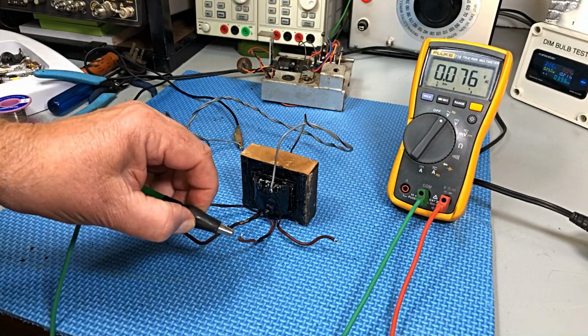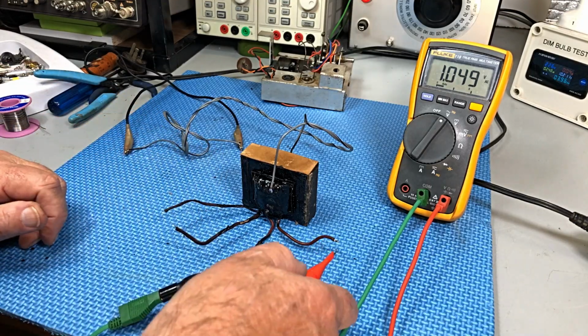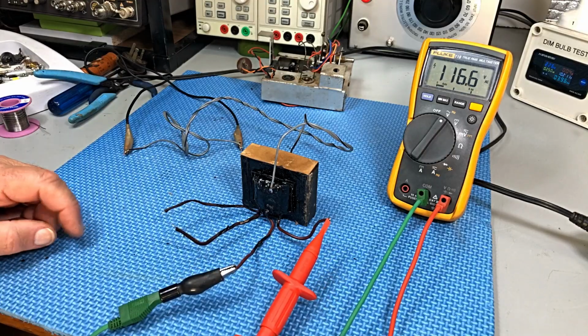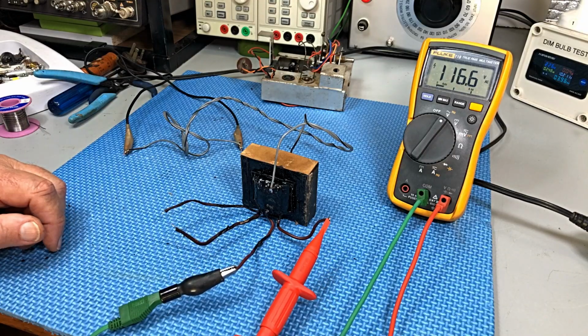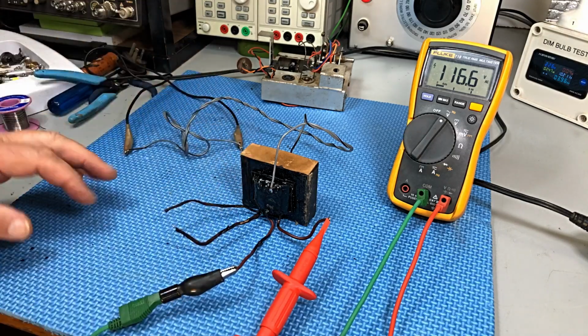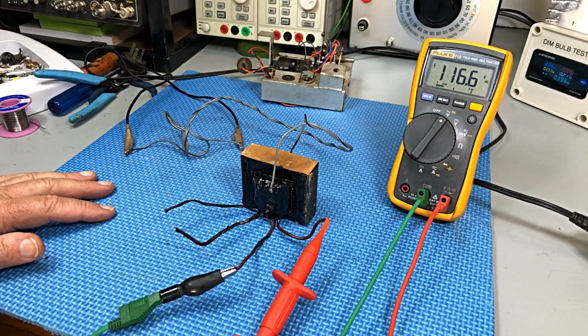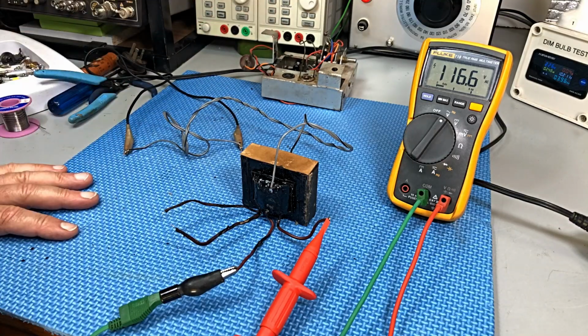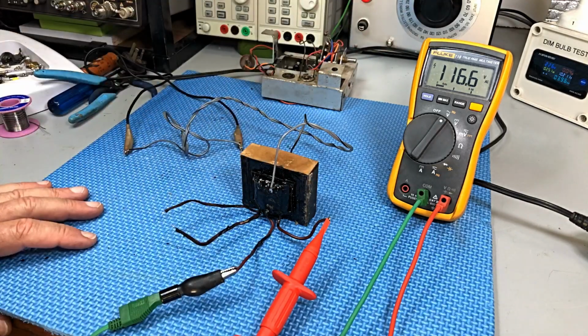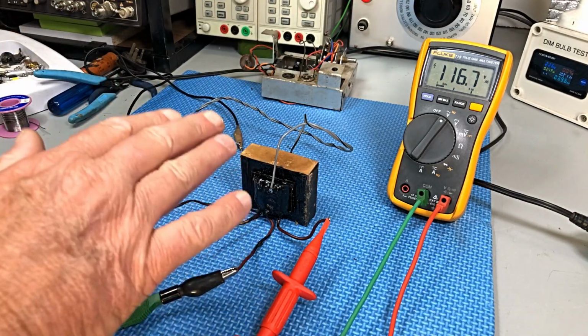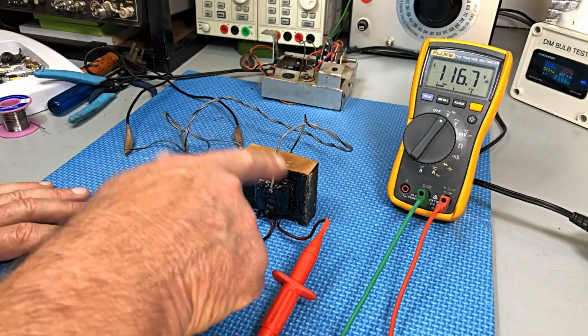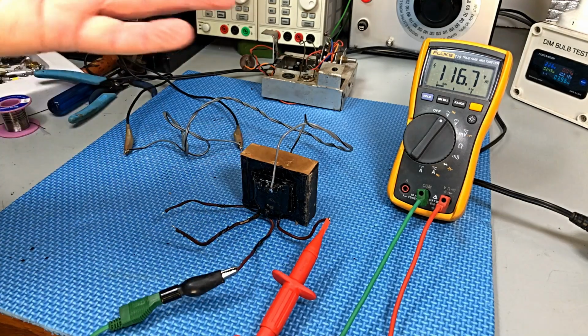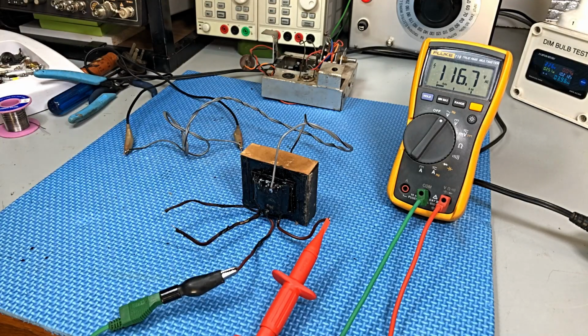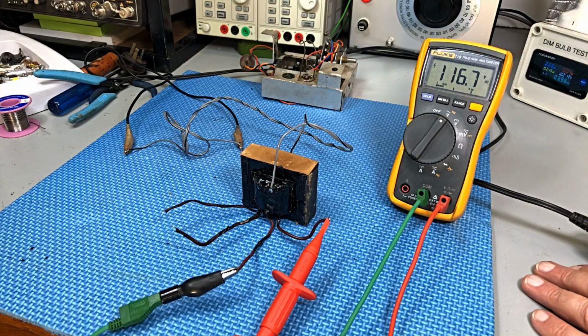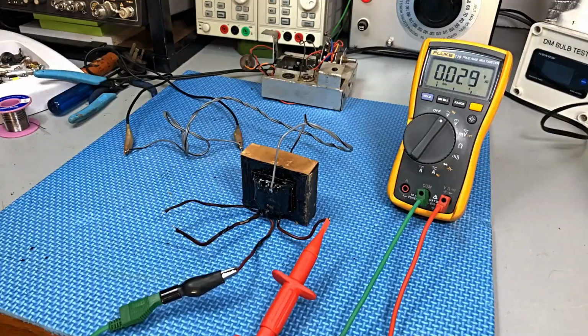Okay, let's see what's on the high tension secondary winding. And we've got 116, which would be around about right. Okay, so I can safely say our transformer is okay. That's good, that's really good. I'm pleased, that had me worried there for a minute that this thing's not working. Okay, 116, 230 volts, and yeah, these don't have a real high HT. We're looking at 90 volts to the radio, so that's around about right.